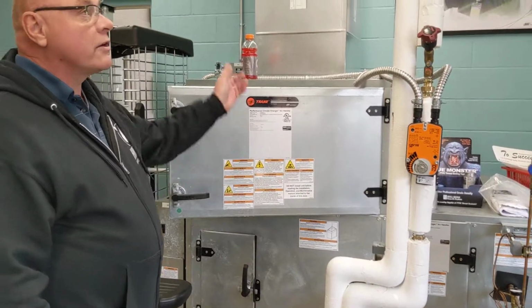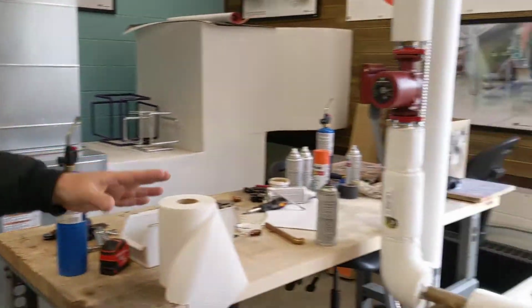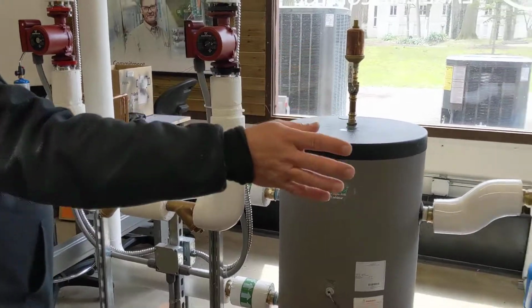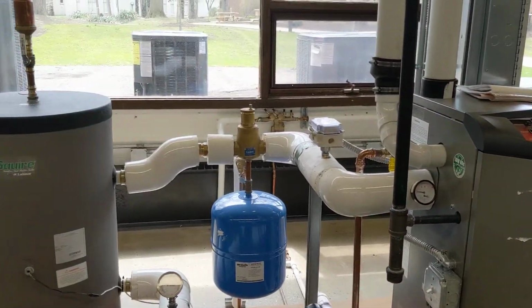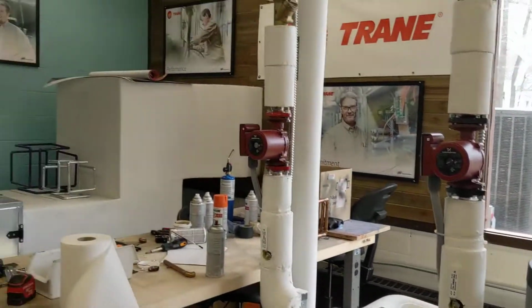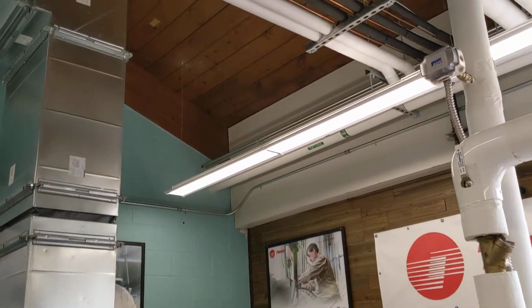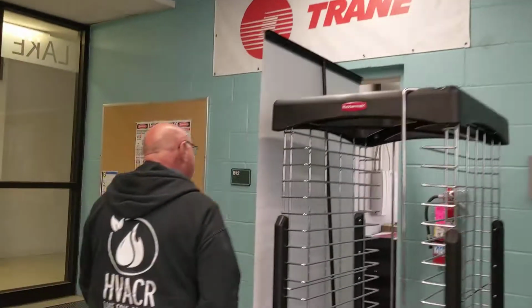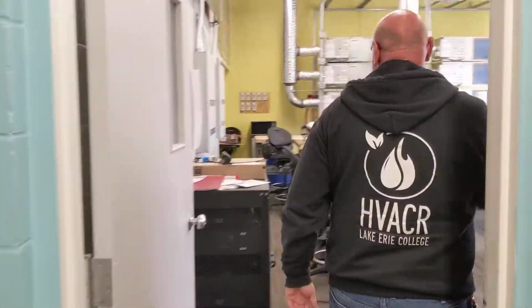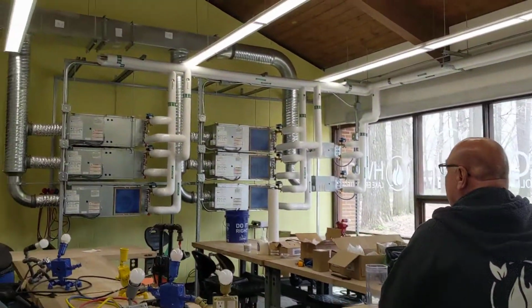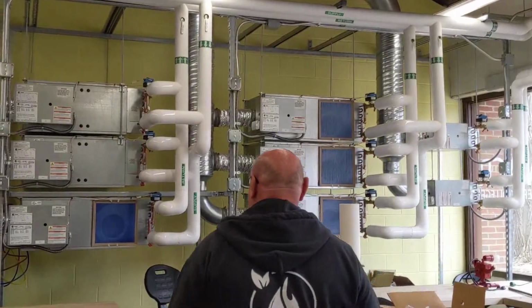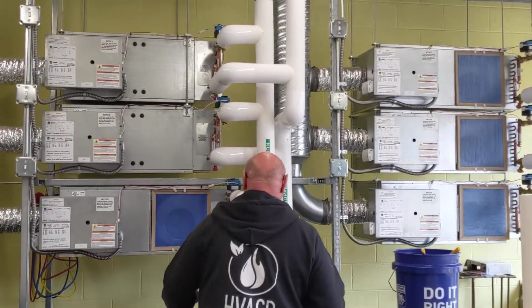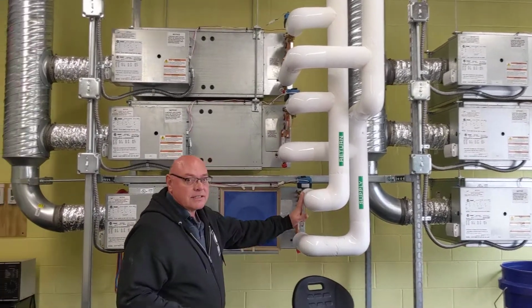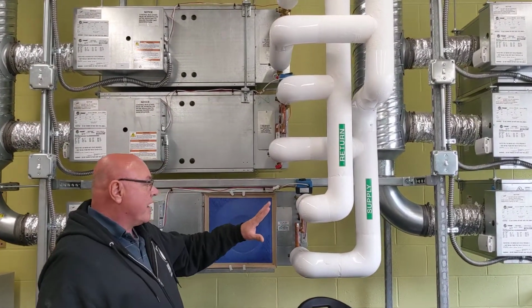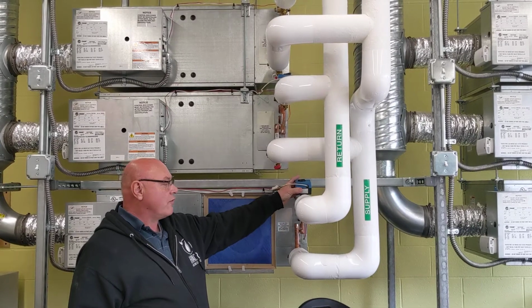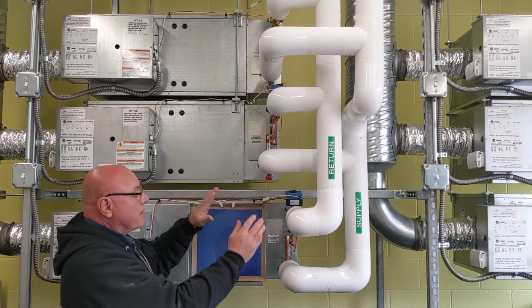So this is our hot water loop here, and that comes back to our heat exchanger, and it picks up heat through the boiler, through the heat exchanger. Then we have another set that branches off, goes into the other side, which we have VAV boxes. Our VAV boxes are normally up inside the ceiling, and you don't see these. And what these do, we can warm up air if we need to, because we still have a control valve here, and here's our heating loop coming to each one of these.